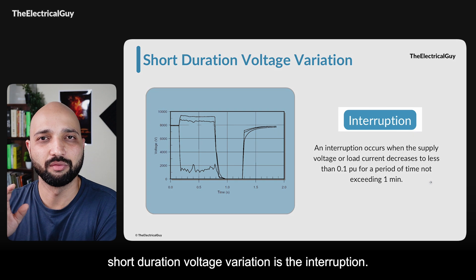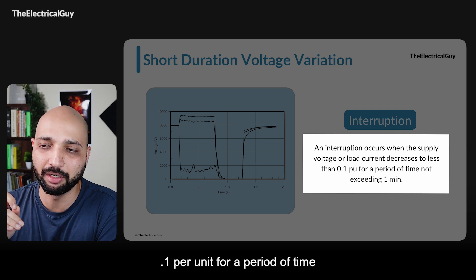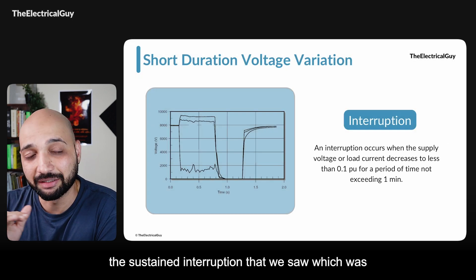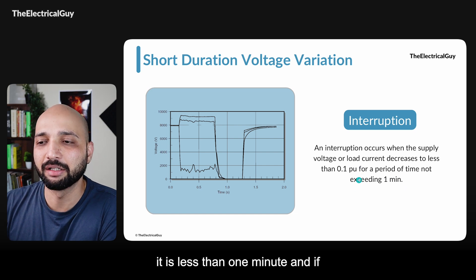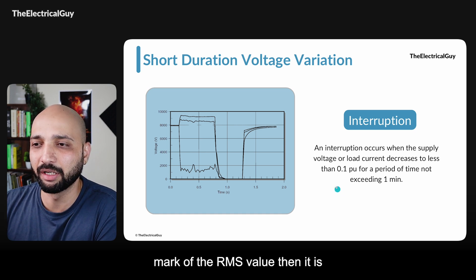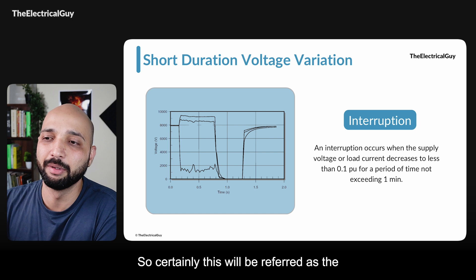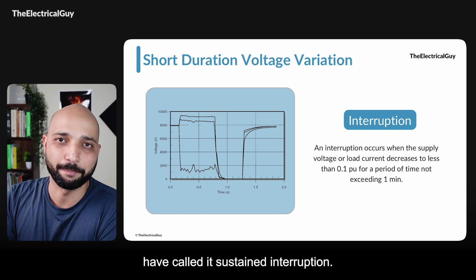The third category in short duration voltage variation is interruption. An interruption occurs when the supply voltage or load current decreases to less than 0.1 per unit for a period not exceeding one minute. This is exactly opposite to sustained interruption, which was more than one minute — here it is less than one minute, and if the voltage falls below the 10 percent mark of the RMS value it is called an interruption. The example shows an issue in one phase causing voltage to drop to a low value but then it raised back to normal after a few seconds, less than one minute — so it is referred to as interruption, not sustained interruption.